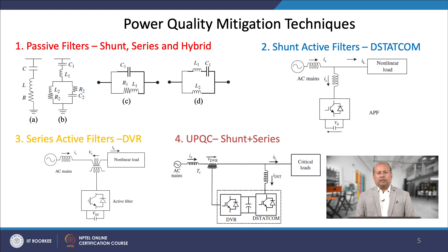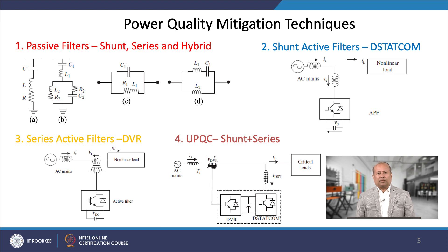Passive filters are extensively used in distribution systems for improving the voltage profile at the point of interconnection, power factor correction, reducing losses, neutral current compensation, load balancing, and better utilization of electrical equipment. Ideally, passive power filters can supply or absorb variable and/or fixed reactive power locally to compensate power quality problems in the system.